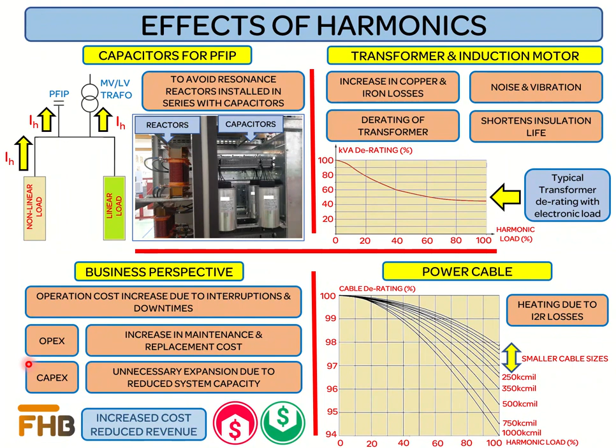It is also important to discuss the business perspective. The high peak currents produced due to the harmonic contents cause nuisance tripping by the circuit breakers and cause production loss. The heating effect produced by the harmonics causes the failure of electrical components, which increases the operational cost on account of repair and replacement. Harmonics cause derating, therefore for new installations, oversizing of electrical equipment is required. A substantial additional amount of investment is required to be paid on account of this oversizing.